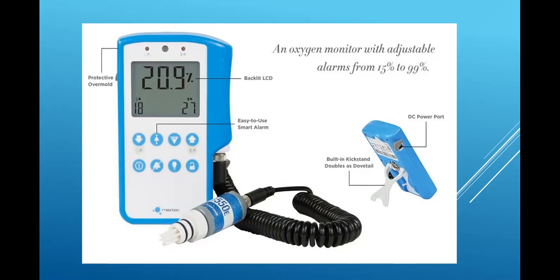That's how you calibrate. So you hit the calibrate button, put it in 100% and go up and down to 100%, and put it in room air and go up and down till you get to room air. And then hit the calibrate button again, now it's calibrated, okay? So whenever I put it anywhere, it's going to read more accurately. But you have to calibrate it first, all right? It's once a shift, okay? But there are also times to calibrate it when I'm trying to calibrate a specific FiO2. And we're going to learn that in a minute.